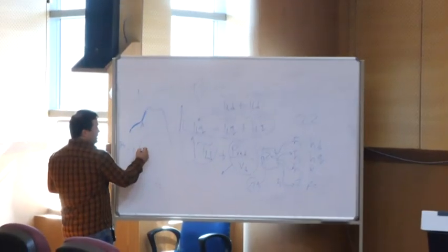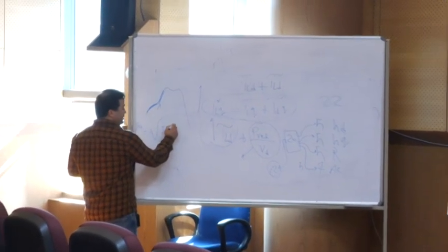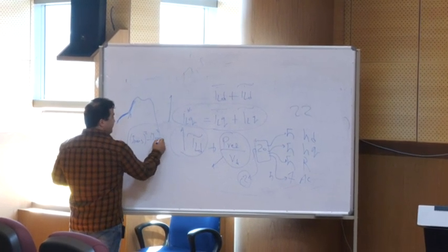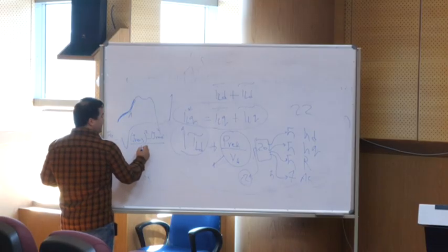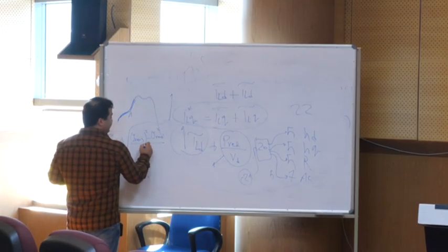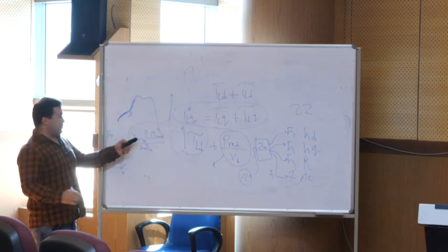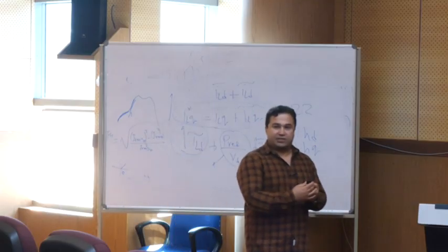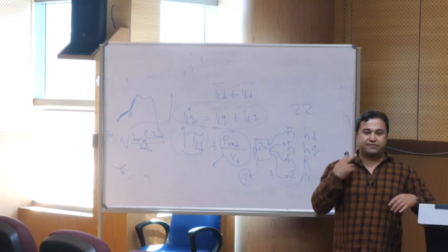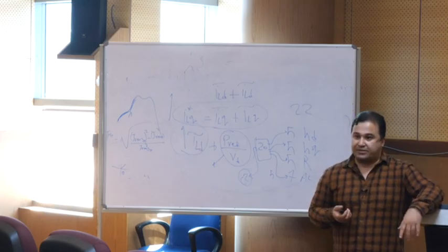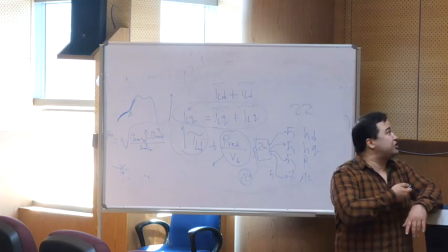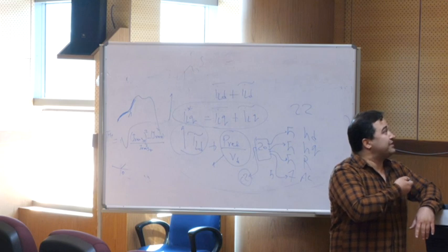For example, THD of a current is I RMS minus I RMS in fundamental frequency to I RMS in fundamental frequency. So it means that if we increase the value of the THD, say that THD of this signal is 25%, it has something like this. Now THD of this system is 22.97, so it has harmonics.